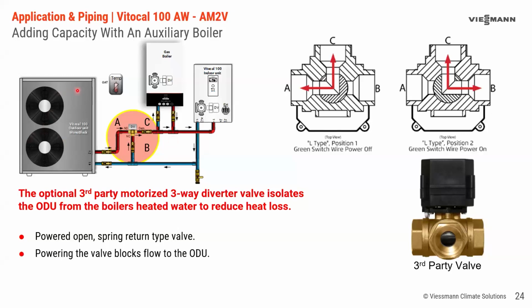And it essentially then blocks the flow of water to the outdoor unit and allows it to recirculate on a shorter circuit here, so that this boiler energy, where the gas we're burning and the electricity we're using to generate heat, isn't being lost to the outdoor unit. Again, this is an optional unit. There are maybe some installations where the contractor or the engineer might say, hey, we want to always circulate water out here for whatever reason.